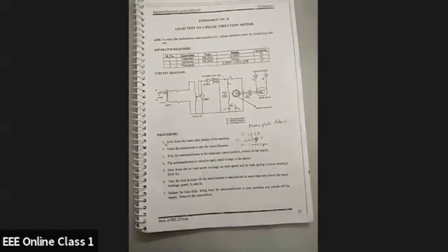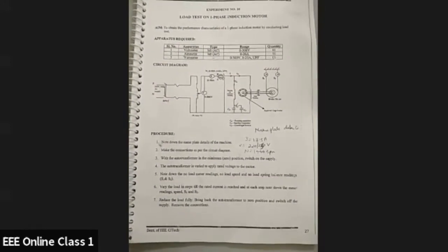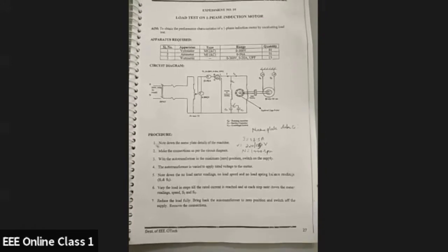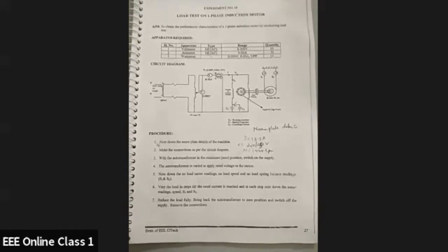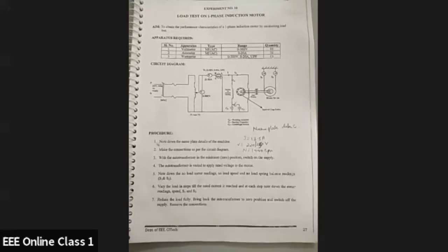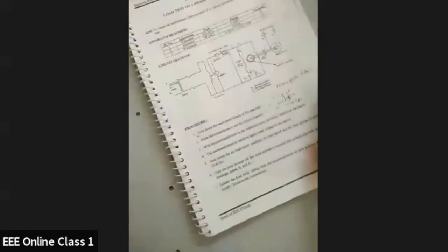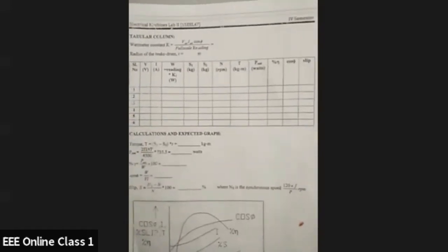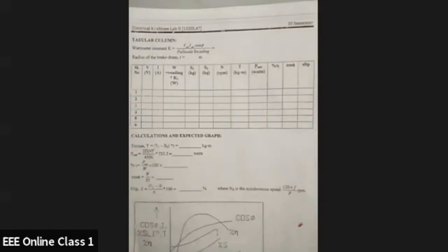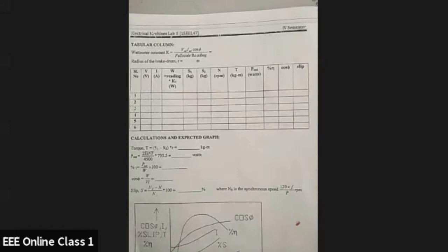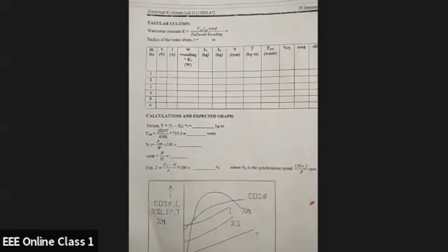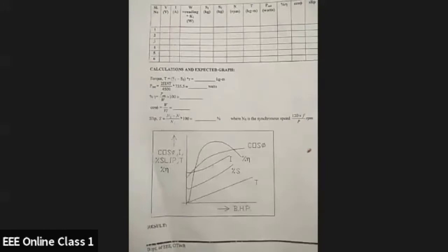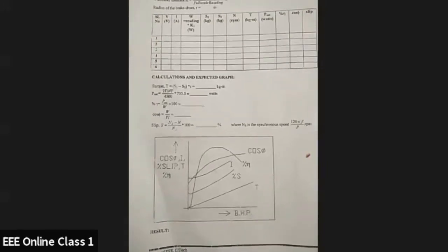the machine. We have to vary the load, and in each step we have to note down the ammeter, wattmeter, speed, and the corresponding load which is applied on the machine. After tabulating these values, using the formulas we have to calculate the other required parameters. As you can see here in the table, we are noting down the voltmeter reading, ammeter reading, the wattmeter reading, and the load which is present on the motor along with the speed. Up to speed we will note down, and the further parameters have to be calculated using the formulae given in the calculations. After that we have torque, output power, efficiency, power factor, and the slip with respect to the machine.